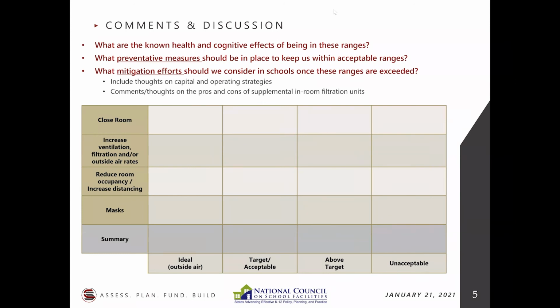And there are so many assumptions that go into carbon dioxide. It's not a yes, no. It's not a black, white type of answer with CO2, as we've already mentioned. So I would advise caution if you're taking that approach and bringing in teachers and staff. You want to keep them informed. You want to educate them, but just throwing CO2 monitors out there, are they calibrated? How precise are they? How accurate are they? The drift, everything related to CO2 monitors is a nightmare.